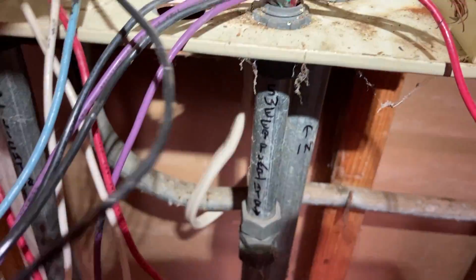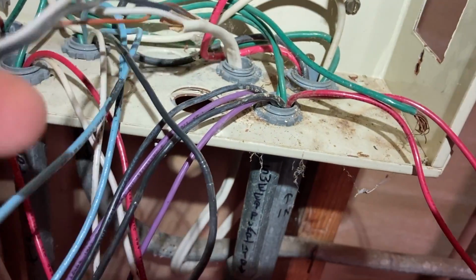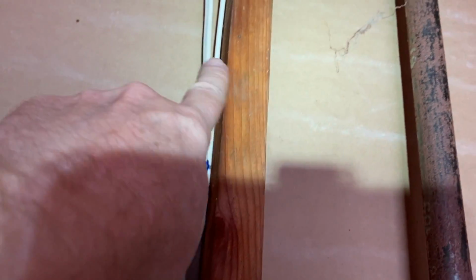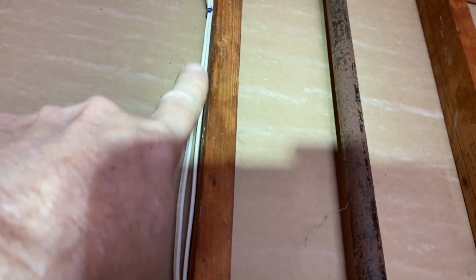The next thing I want to do - this piece of Romex is a relatively recent addition. I'll show you down there. It loops under that pipe, and it's not anchored well, and there's no clamp or anything on this. It goes up to this box here where it's split into two: one to the hot tub and one to the lights and whatever else in the bathroom next door.